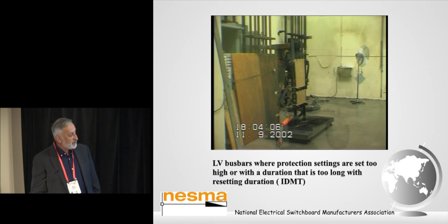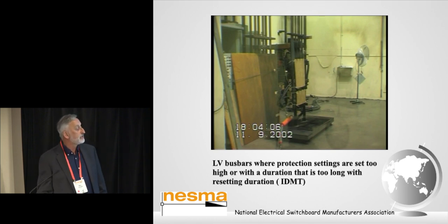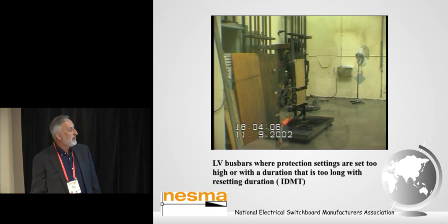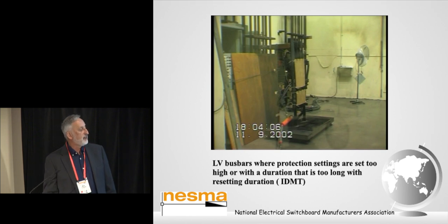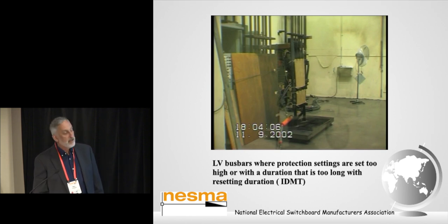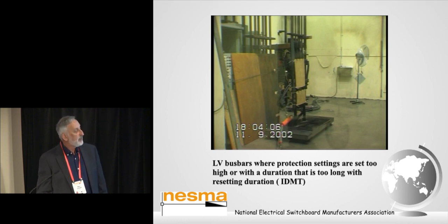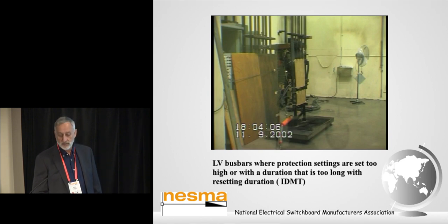But what we have is protection settings were set too high, and you've got a duration where it was an IDMT protection relay that was resetting. So with a 400 volt test, the arcing starts moving away from the source of the supply, and it will self-extinguish. But if the conditions for arcing are still present, it will continue until protection operates. So we'll see what happens.